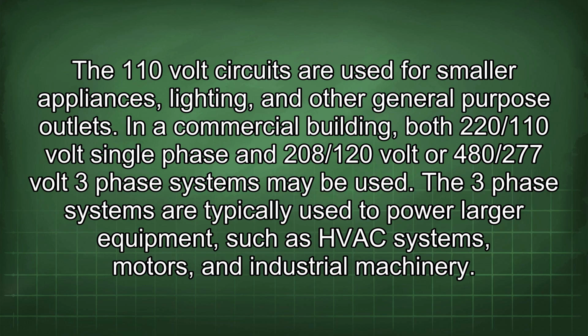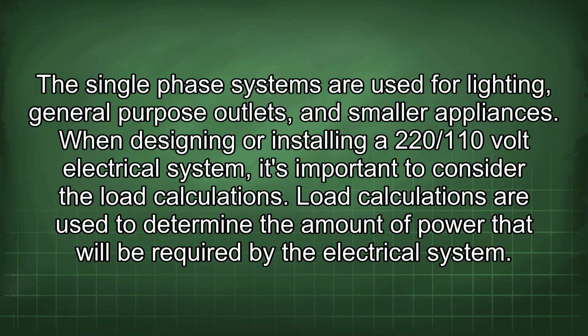In a commercial building, both 220/110 volt single-phase and 208/120 volt or 480/277 volt three-phase systems may be used. The three-phase systems are typically used to power larger equipment such as HVAC systems, motors, and industrial machinery. The single-phase systems are used for lighting, general-purpose outlets, and smaller appliances.